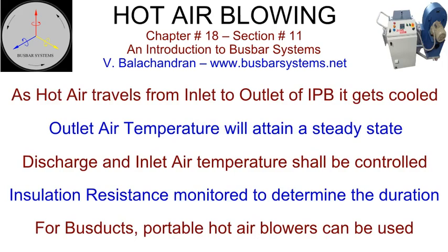The outlet air temperature will attain a steady state temperature over time. The discharge and the inlet air temperature from the hot air blowing system shall be monitored and controlled.